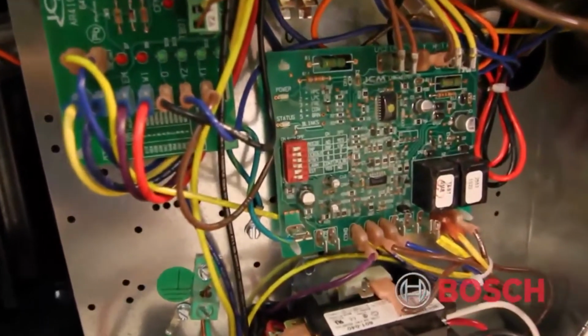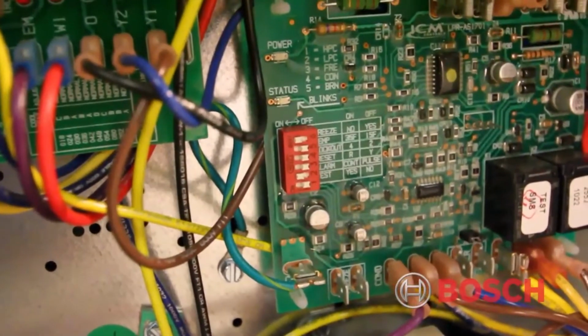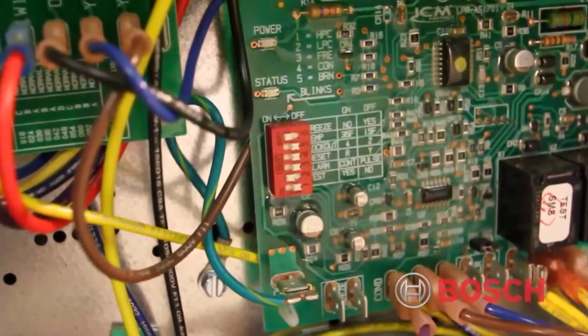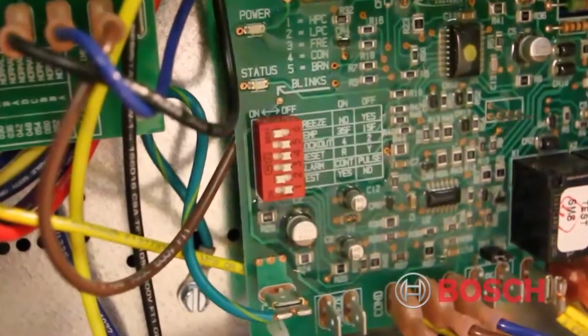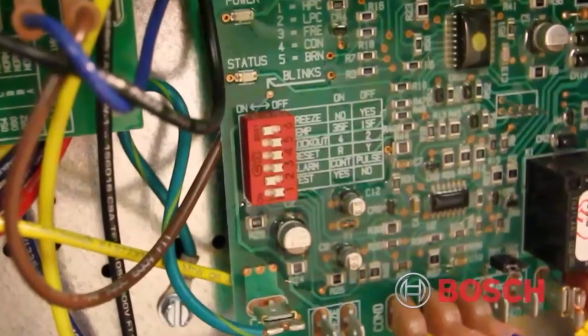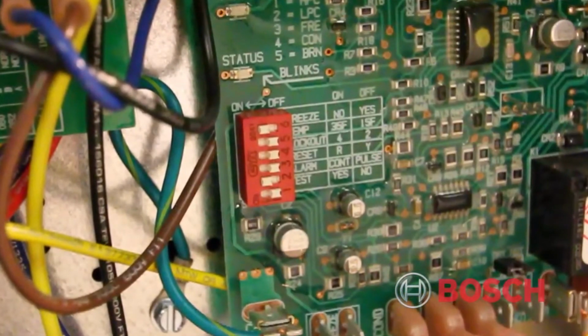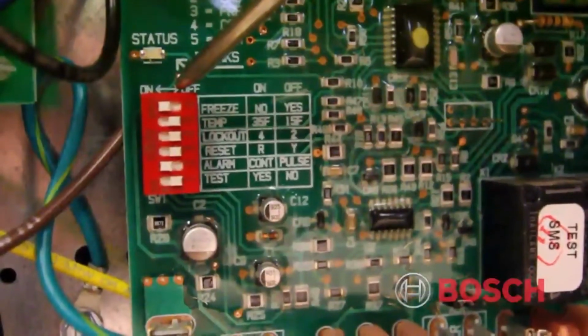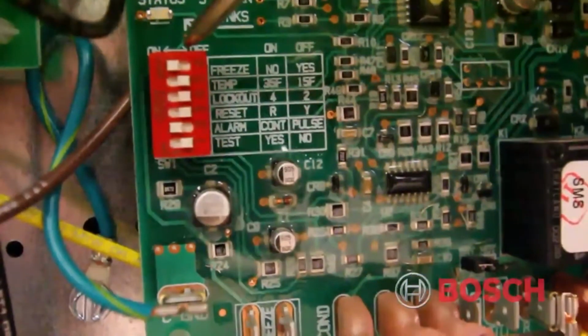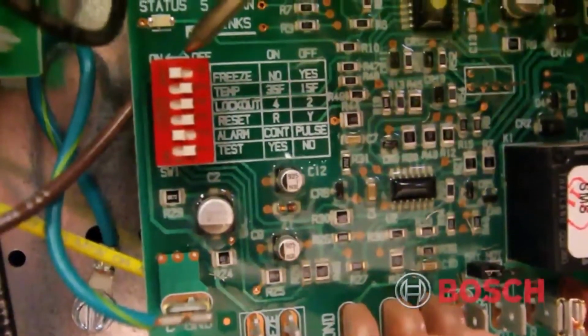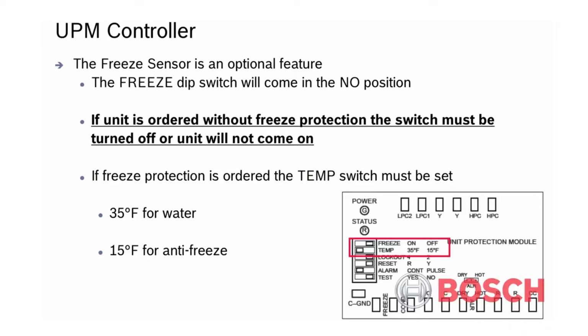On the UPM control board, there are 6 dip switches. You should consult the installation manual to determine the proper position for each of these switches so that all of the safeties will function properly. The first switch at the top of the board is the freeze protection switch. It is going to come in the no position, which means there is not a factory installed option of freeze protection. If you have the factory installed option of freeze protection, you need to put this switch in the yes position so it will be functional.